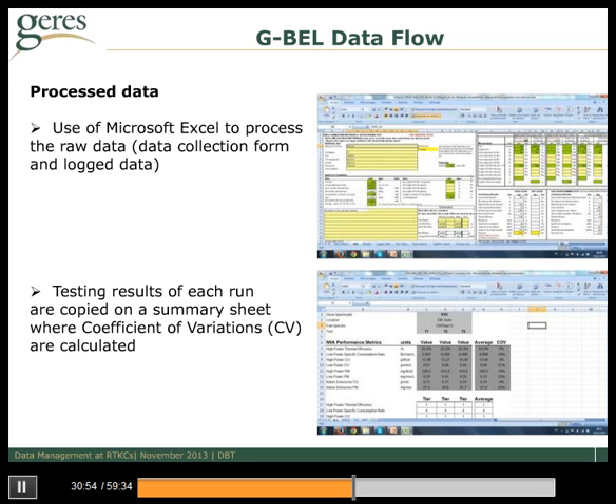So once we get the raw data, we are processing them using Microsoft Excel. We are using the processing sheet specific to the LEMS, where we are entering the data of the data collection sheet and importing the CSV file. So once processed, testing results of each run are transferred to a summary sheet in order to calculate coefficient of variation. We are considering a series of runs valid when variation on fuel use is 10% or less, and variation of CO and PM emissions are 25% or less.